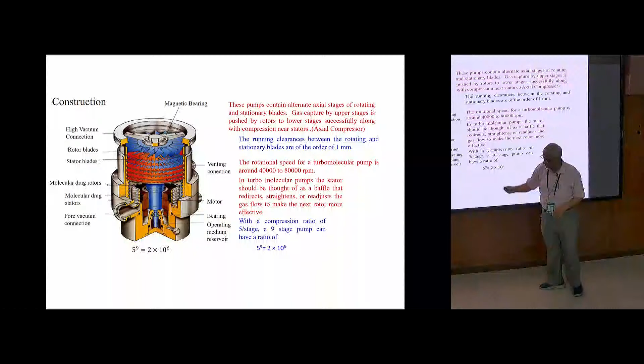Anyway, so this is how you have understood some production, and pumping speeds are independent of pressure, because any number of molecules I can catch, minus 8 or minus 9, whereas the rotary pump fell because of the compression expansion principle. Here there is no compression expansion principle. Any number if it comes, I will pump. If fewer come, the higher the vacuum, fewer will come, I can easily pump them. Like if I can teach 200 people, 20 people is nothing. Like that confidence develops.